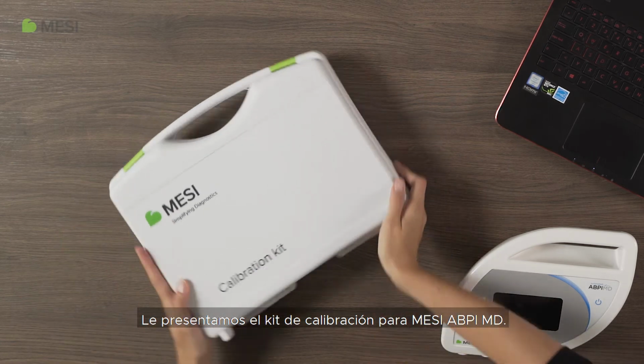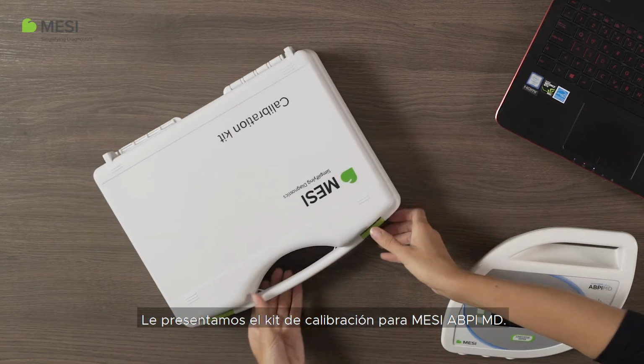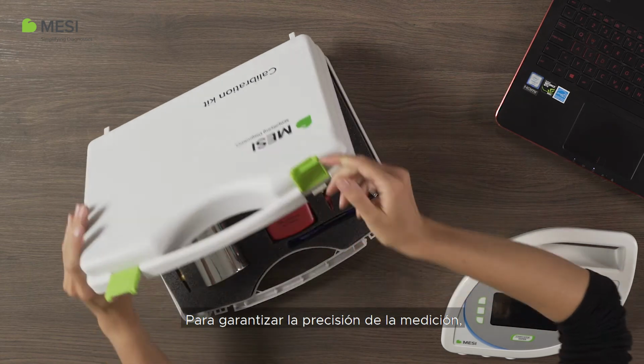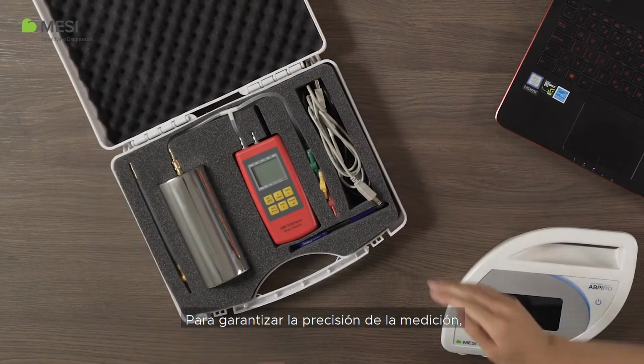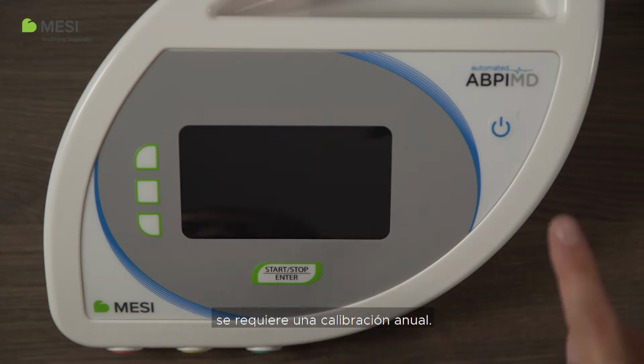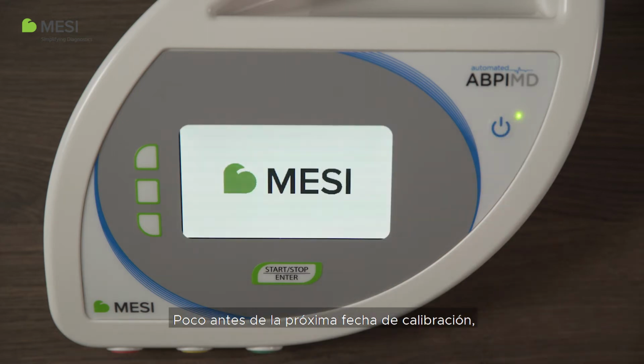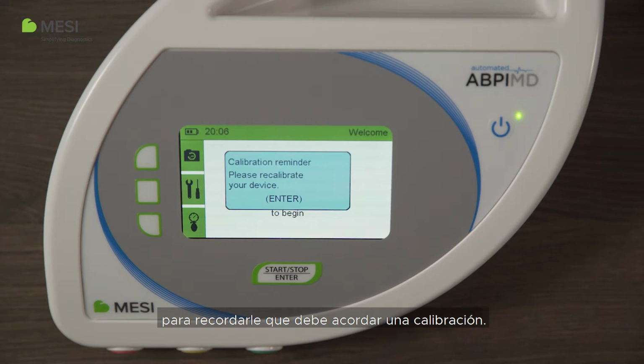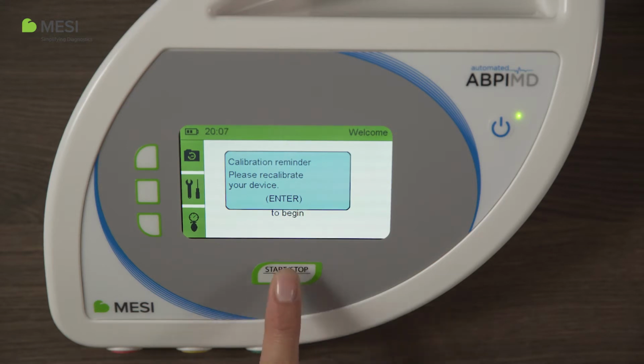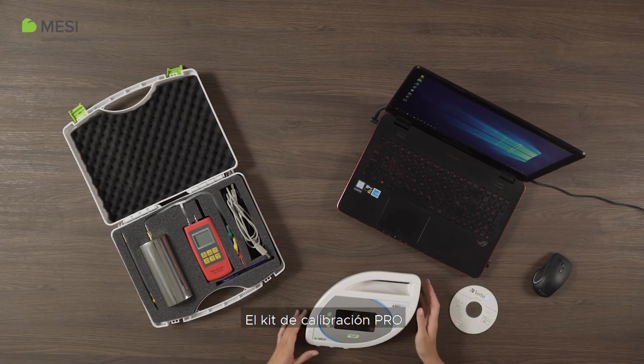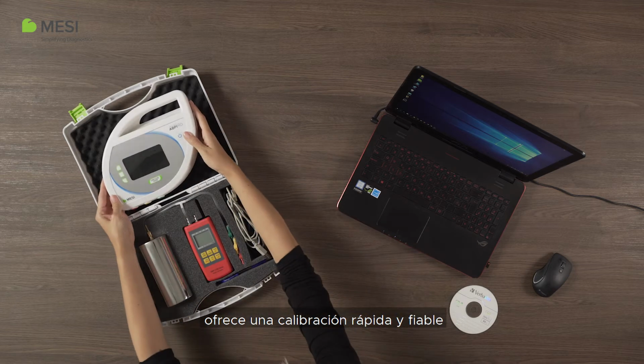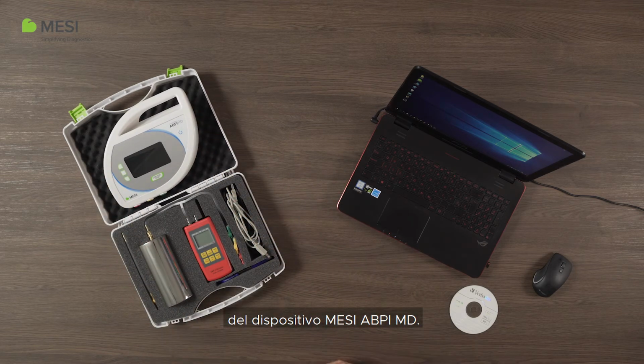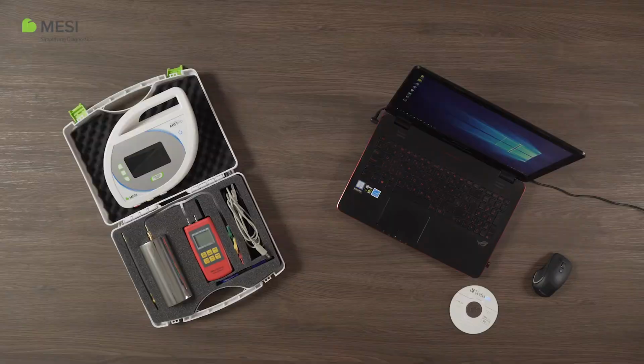This is the calibration kit for MESI ABPI MD. To ensure the accuracy of the measurement, an annual calibration is required. A calibration reminder will trigger shortly before the next calibration date to remind you to arrange a calibration. Calibration Kit Pro provides a quick and reliable calibration of the MESI ABPI MD device.